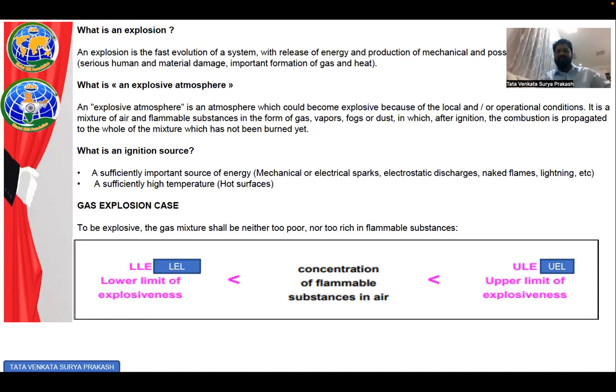A complete tank farm, because there is no lightning protection, and a tank caught fire, and subsequently it went to a disastrous incident. A sufficiently high temperature or hot surface is also an ignition source. So what is the case of an explosion? To be explosive, the gas mixture shall be neither too poor nor too rich in flammable substances. So we all heard about LEL, the lower explosive limit, and the concentration of flammable substances in there, and upper limits. For example, if you take hydrogen, we will always say the lower limit is 4.5 and the upper limit up to 75%.